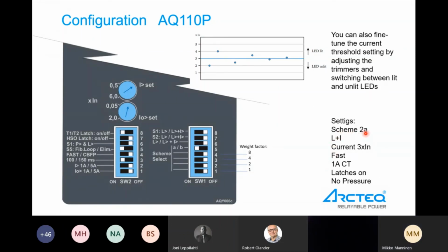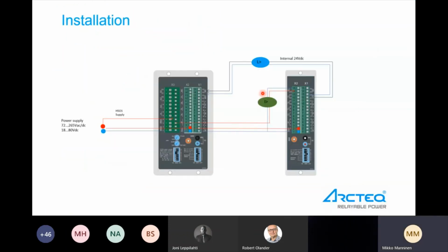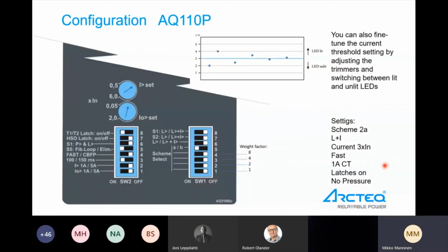Scheme 2A is the scheme from here. When we select from these DIP switches, we have a weight factor here. It's binary coded, so it's like 1, 2, 4, 8. So if we want to have a scheme 9, we will have 8 plus 1. But now we have a scheme 2A. We should have this one on, and then we should have this one on. Then we have 2A. So this is actually very simple and straightforward.